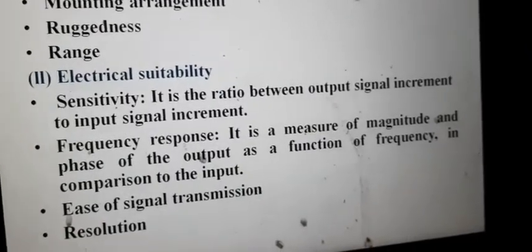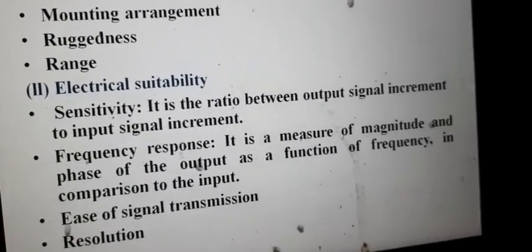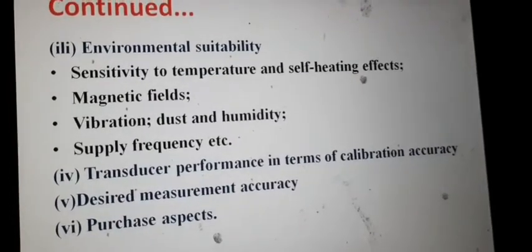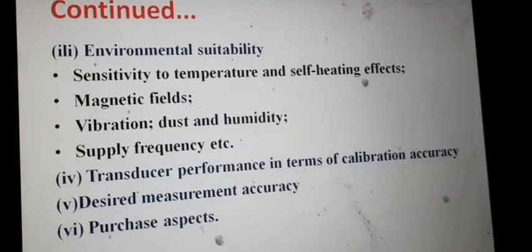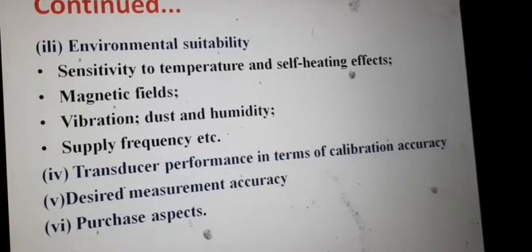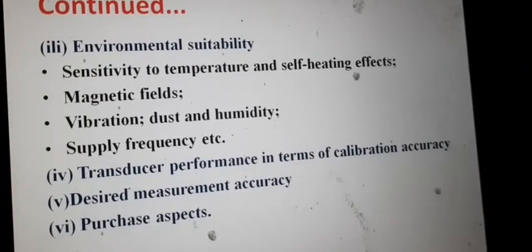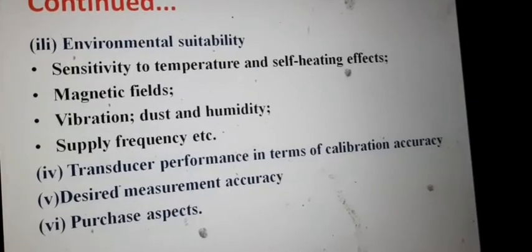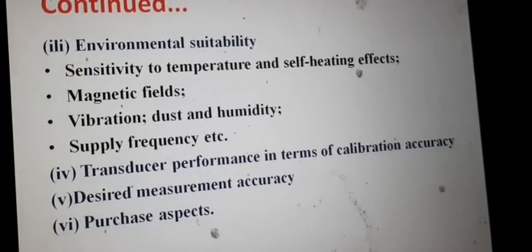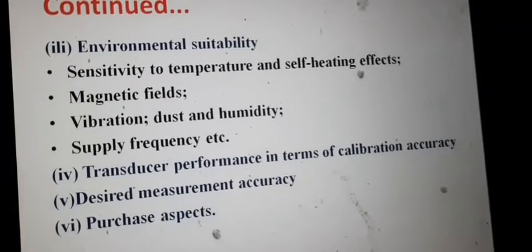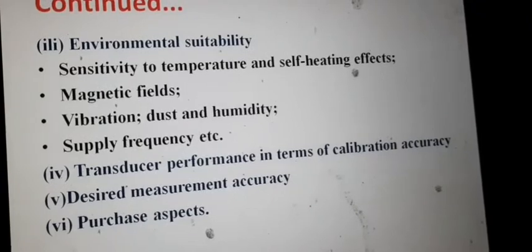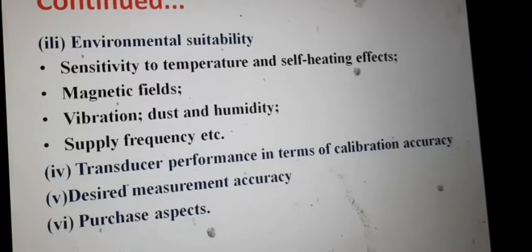Next is environmental suitability. The transducer should not be affected by environmental conditions — it should not be sensitive to temperature, should not generate heat within itself, and should not have its readings changed by magnetic fields, vibration, dust, or humidity. All these things should be considered while selecting a transducer.